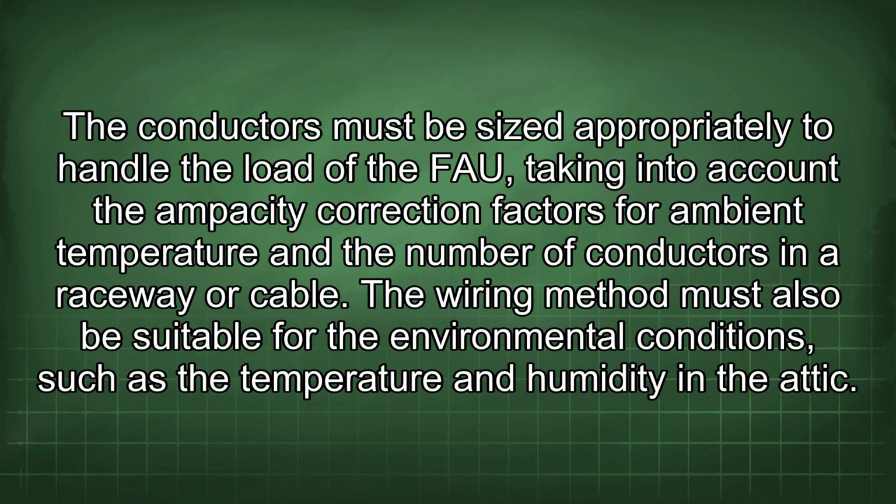The conductors must be sized appropriately to handle the load of the FAU, taking into account the ampacity correction factors for ambient temperature and the number of conductors in a raceway or cable. The wiring method must also be suitable for the environmental conditions, such as the temperature and humidity in the attic.